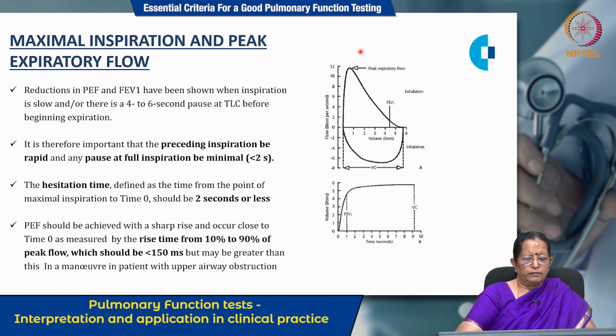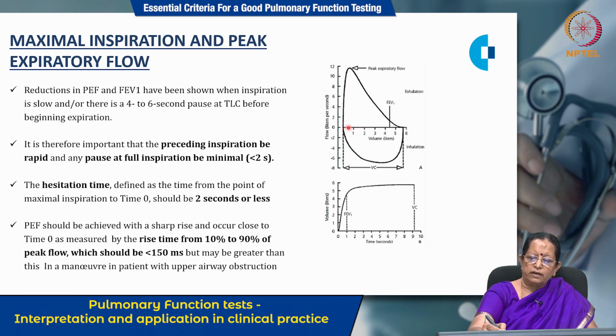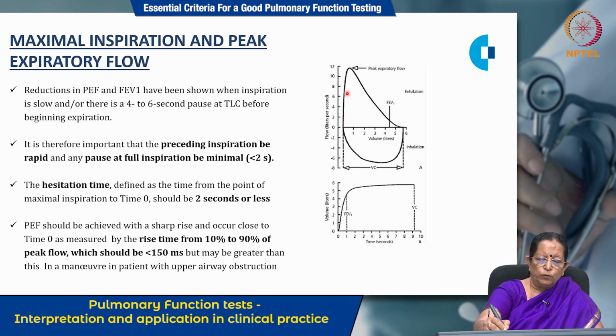Then hesitation time, that is the time from the point of maximal inspiration to time 0. Time 0 is here, from maximal inspiration when the patient starts to expire. So, that time should be 2 seconds or less. Then this peak expiratory flow should be achieved with a sharp rise and occur close to time 0. This is time 0 when he starts expiring. It should have a sharp rise and occur close to time 0, and the rise time from 10% to 90% of the peak flow should be less than 150 milliseconds. But in a patient with upper airway obstruction, this can be greater.